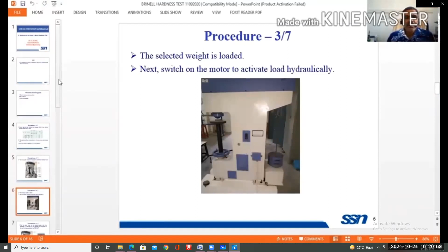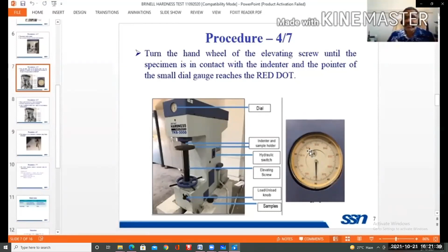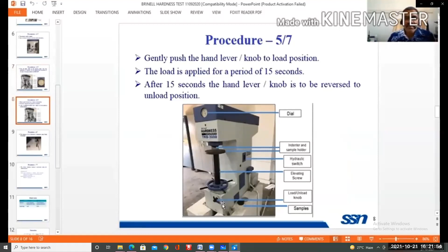indenter. Once the indenter makes the initial contact, here is a big dial, and inside there is a small dial, and an indicator is also there. When the initial setting is over, it is confirmed by the indicator, which has to reach the red spot. Then the setting is over. After that, we have to apply the load. This is the loading knob. You rotate it clockwise, the load will be applied, and you wait for 15 seconds. After 15 seconds, you remove the load.